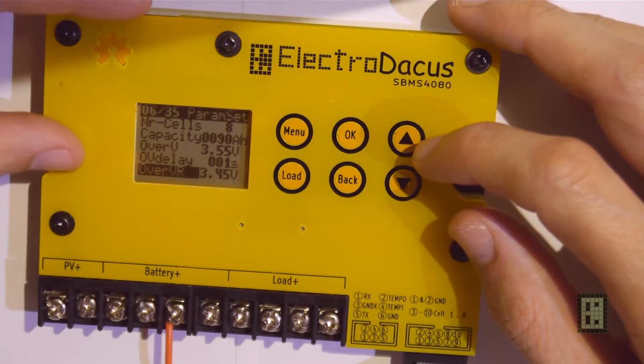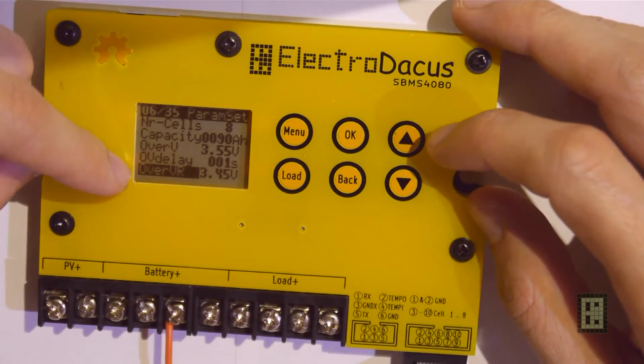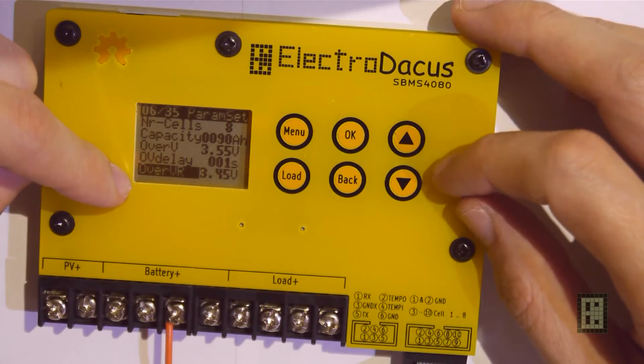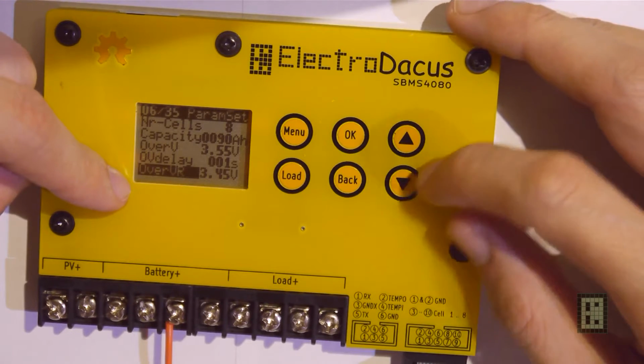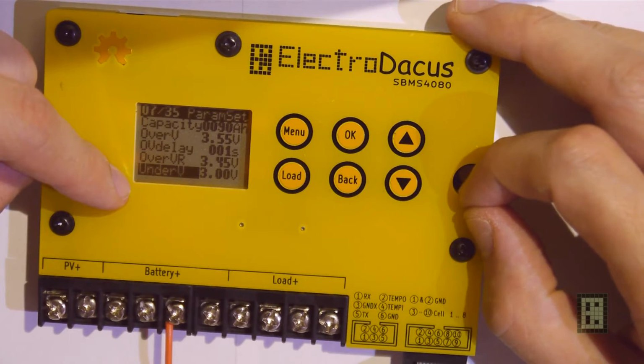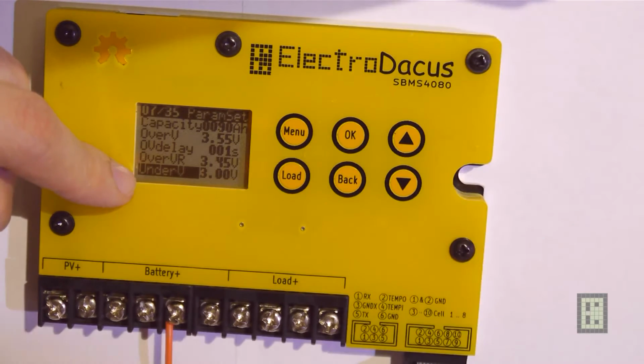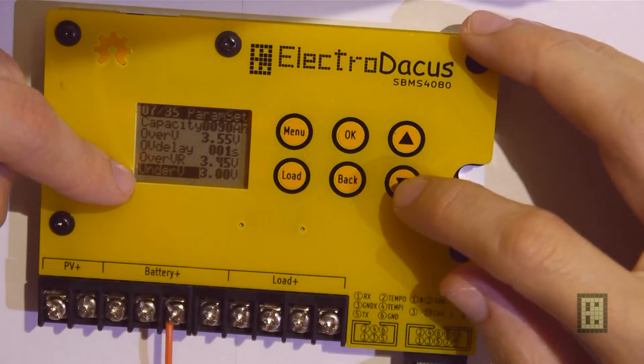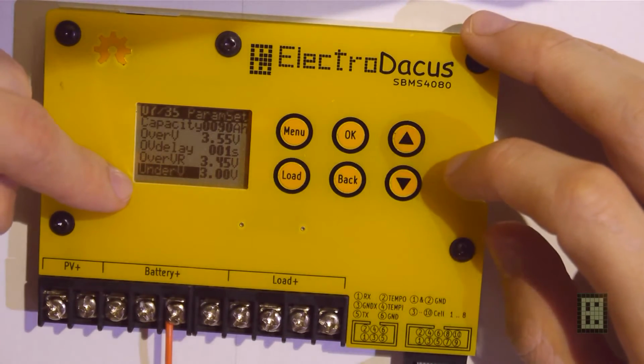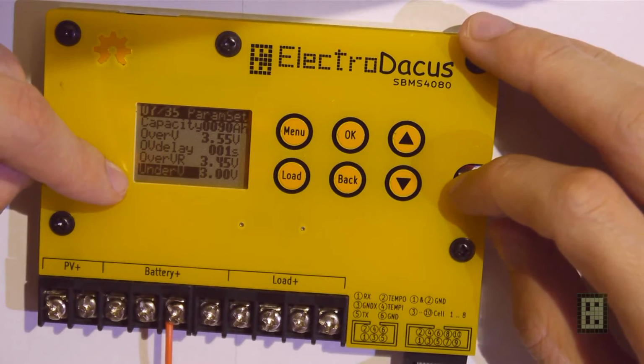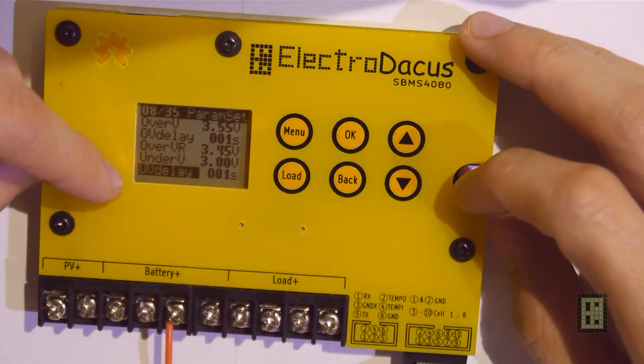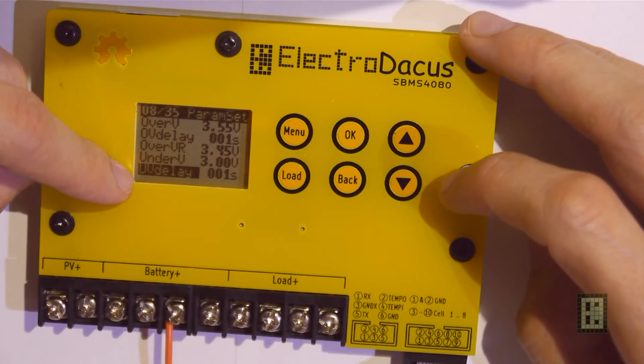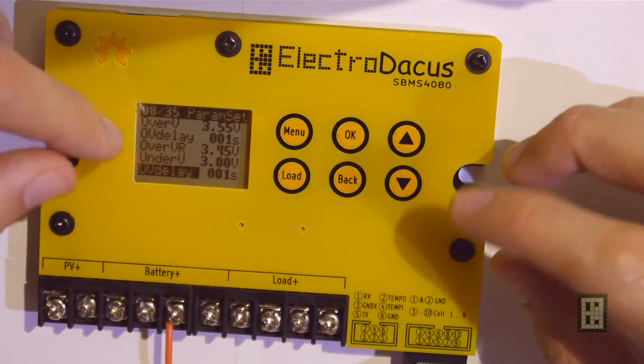And this is over voltage recovery. It will start charging again when it hits this threshold that you set here. Then this is under voltage. Here it will disconnect the load when any of the cells gets to this level, so the lowest cell will win here. And then again the delay, under voltage delay, again how many seconds to wait.